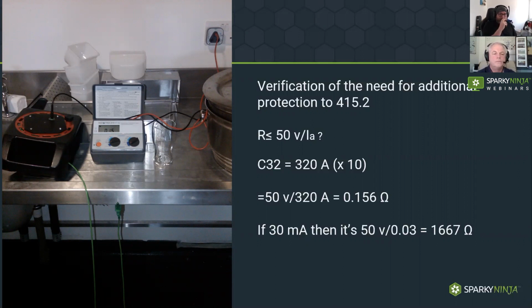The reason I did this was to look at the need to consider 415.2, because we have an inspection checklist to tick confirming supplementary bonding is present if needed. But the question is, do we actually go around locations and ask ourselves: can we touch exposed and extraneous conductive parts simultaneously, or exposed conductive parts of different systems, which we think about in temporary systems? There's little to no coverage or mention of this application in the 2391.